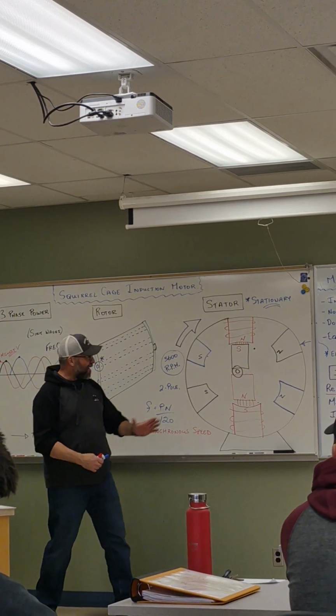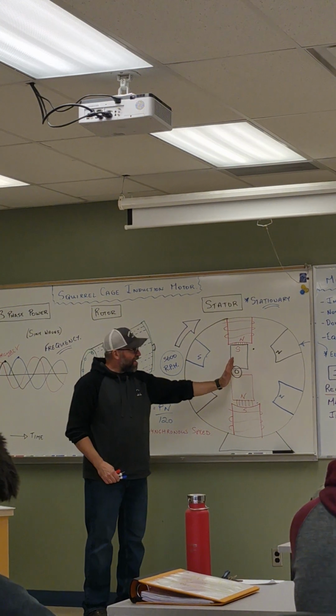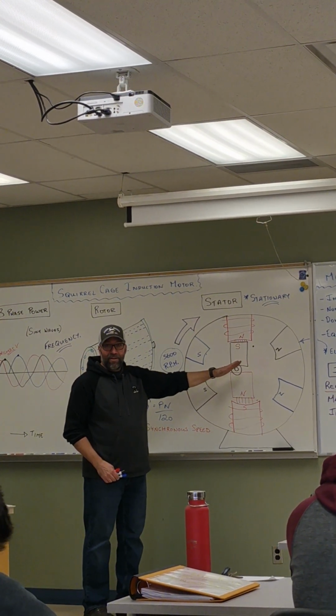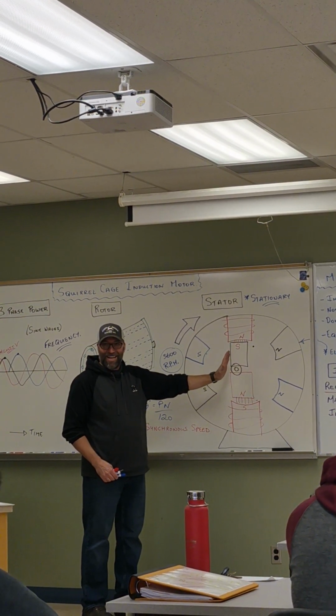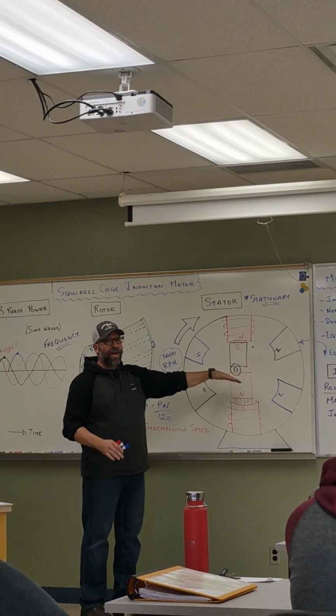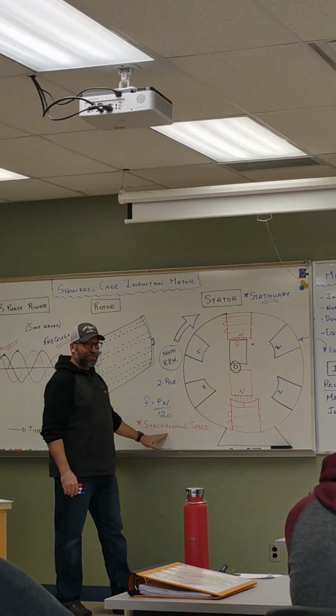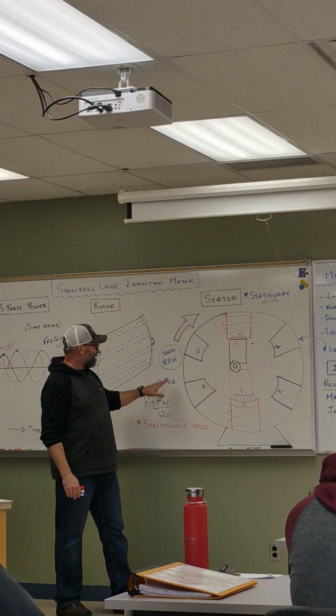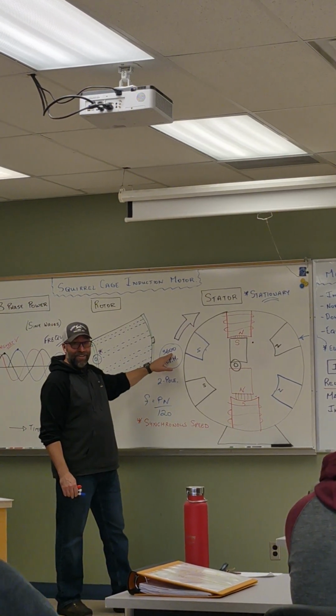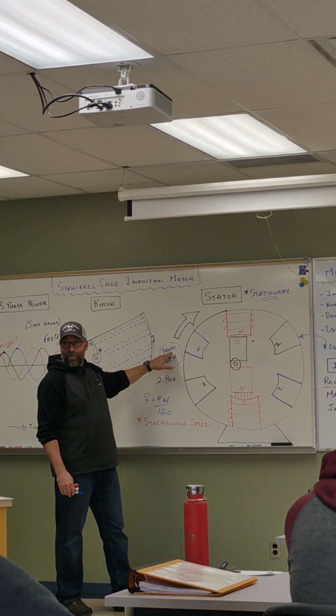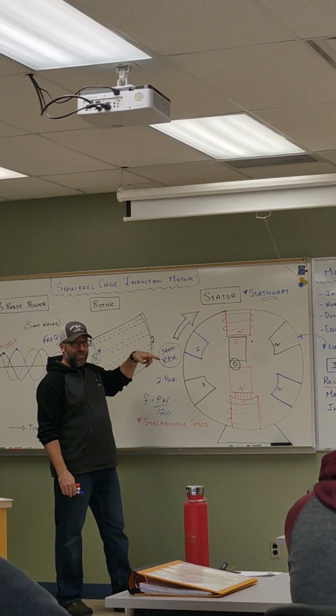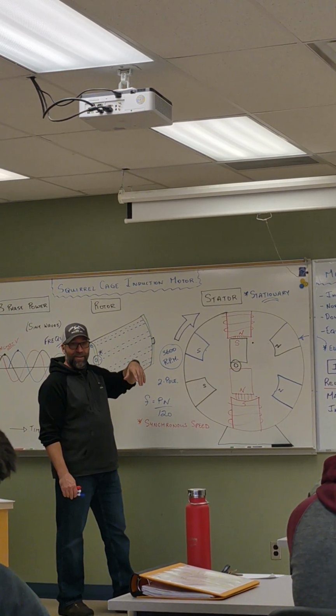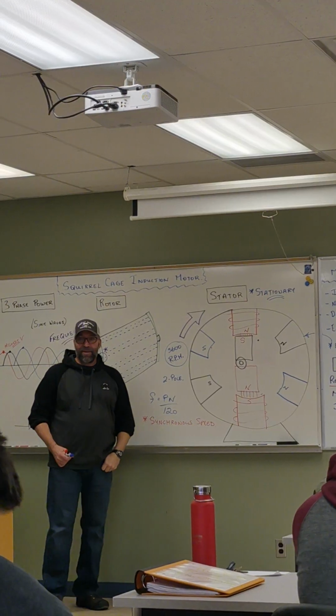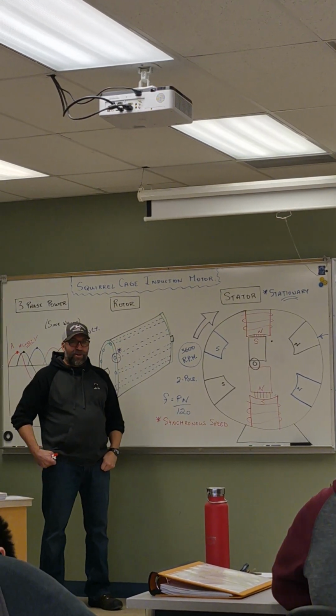Now I've got an electromagnet in the rotor that hangs on to the electromagnet of the stator, and when the stator moves, the rotor moves at exactly the same speed. Hence the term synchronous motor - it will turn at synchronous speed, it turns at the calculated speed. Whereas a squirrel cage will never turn at the calculated speed, it's always going to be 5 to 15% less than that. So the synchronous motor all of a sudden turns at 3,600 RPM.